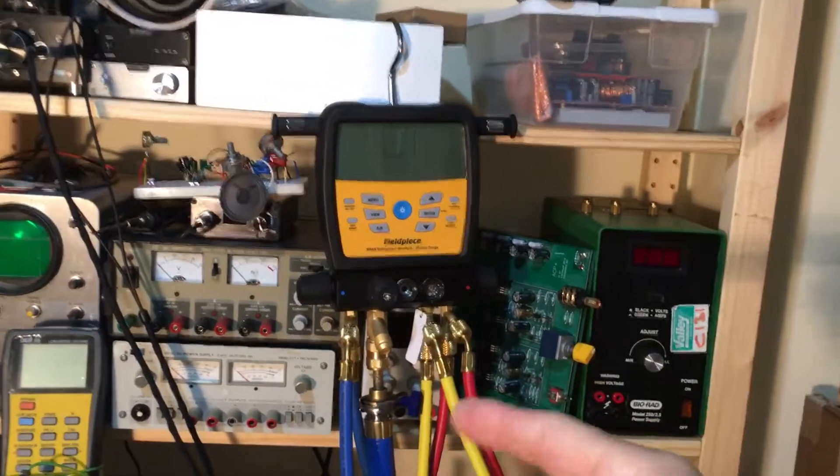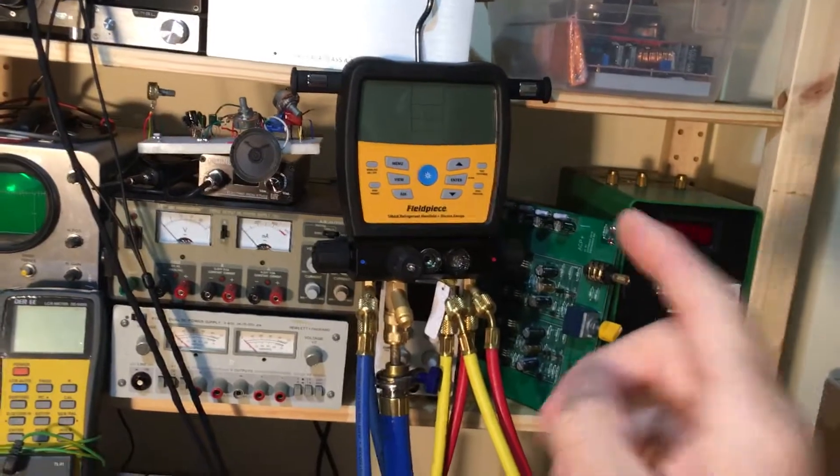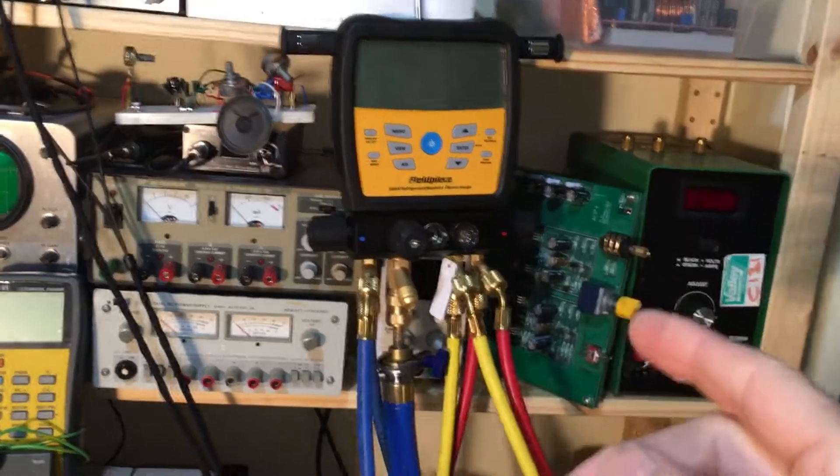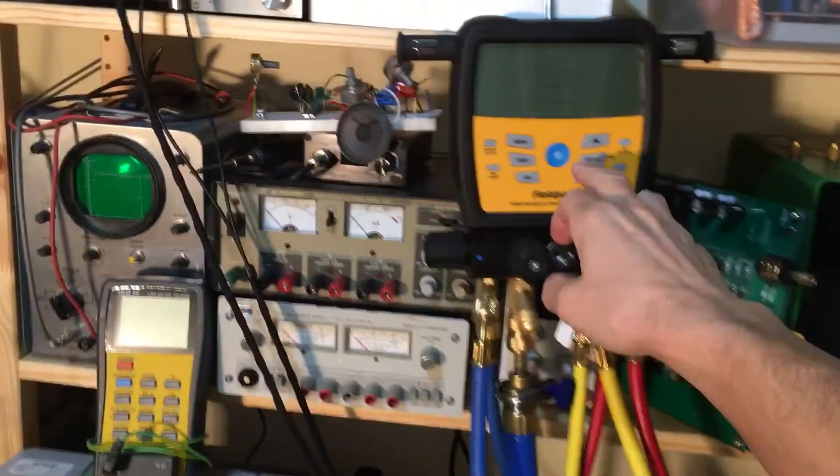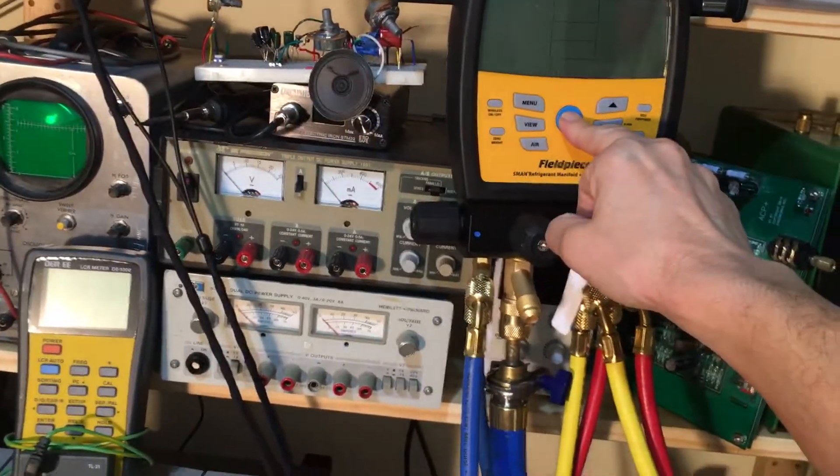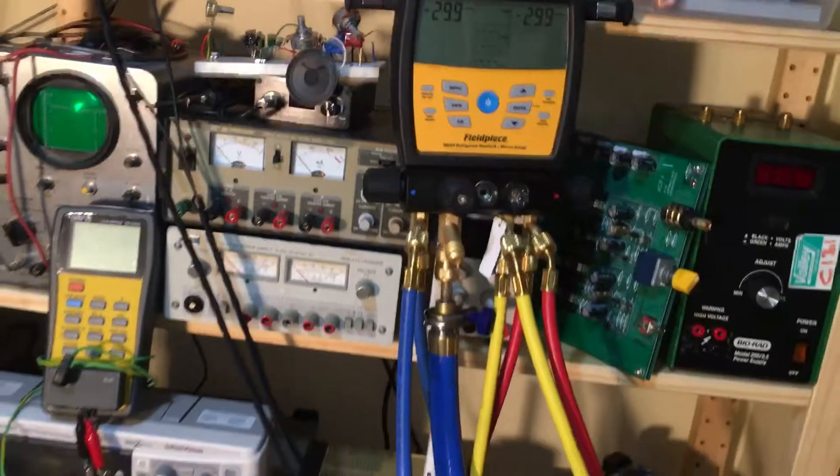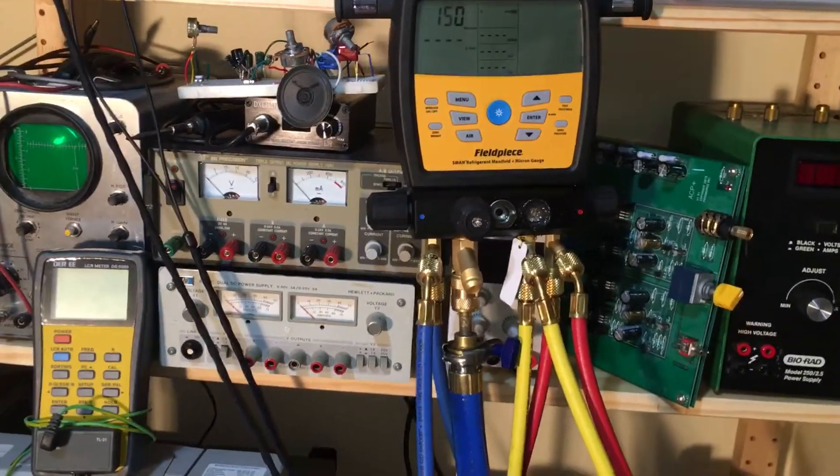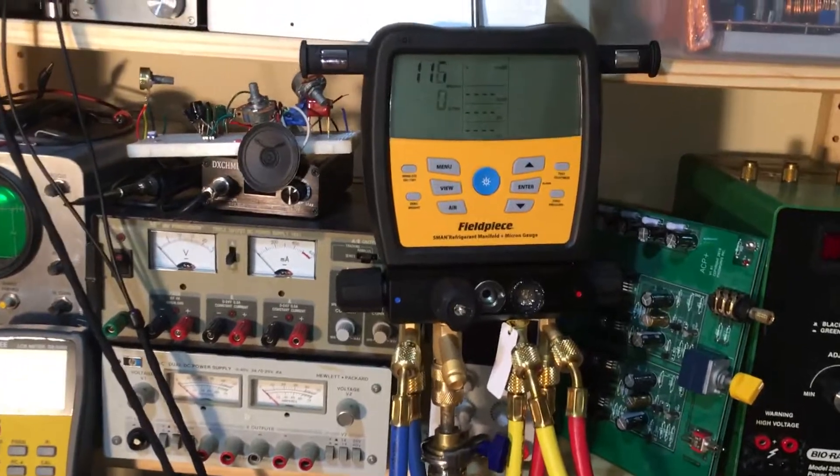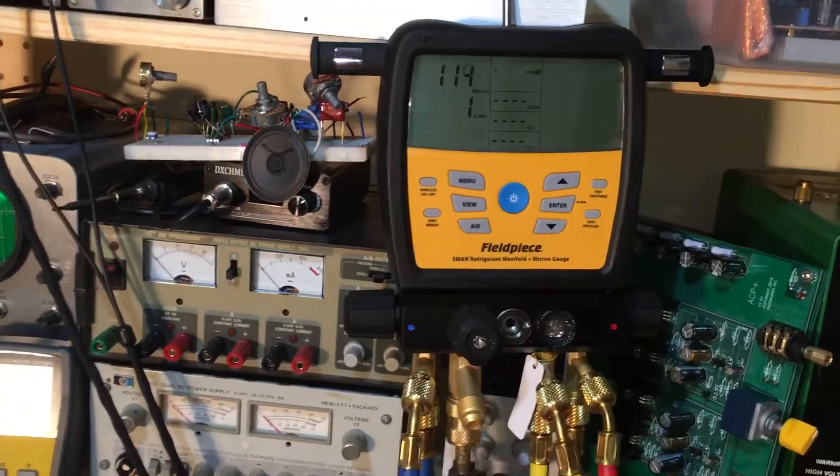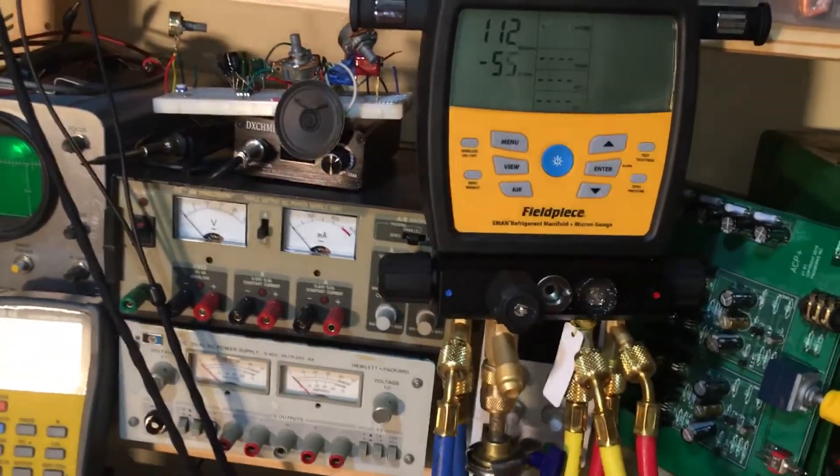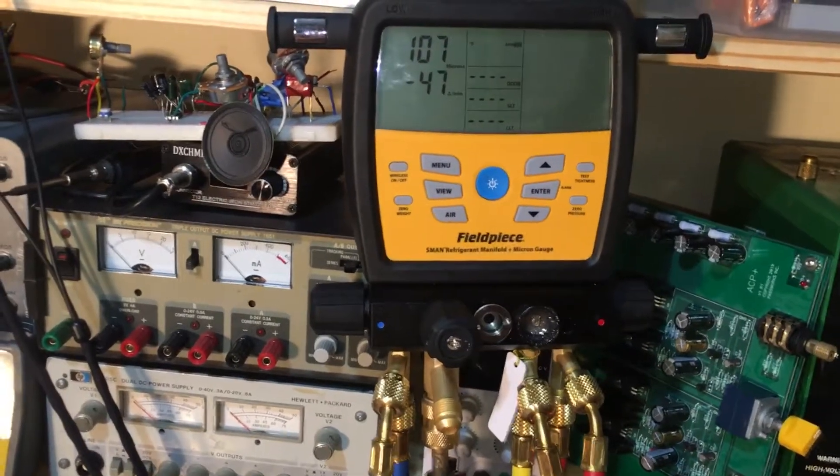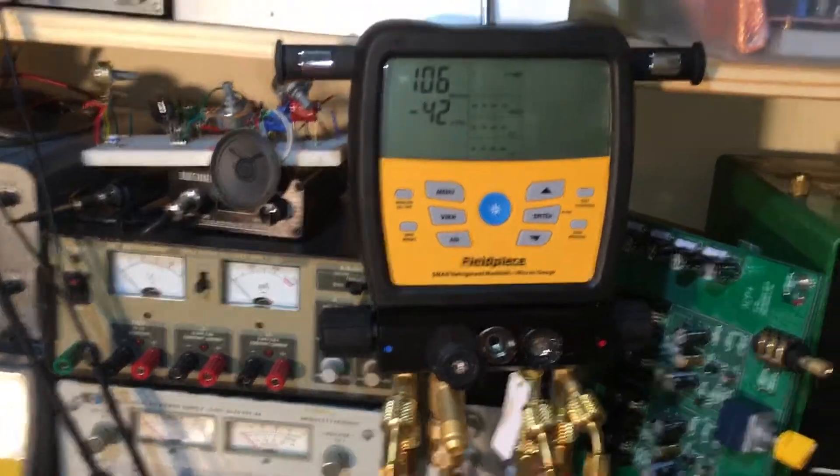Okay, from the last video, now it's 7 a.m. the next morning. Let's take a shot of what the decay rate from 13 microns is to now. We're coming down, we're over 100 microns, so we're good to go.